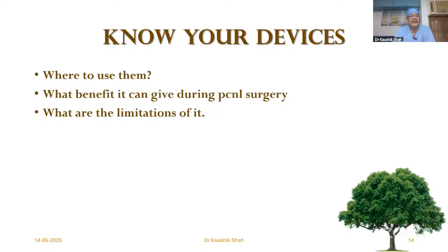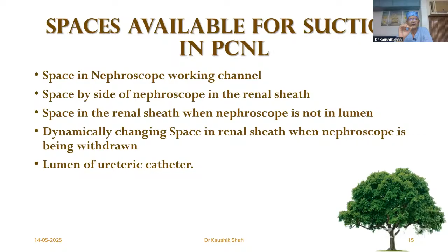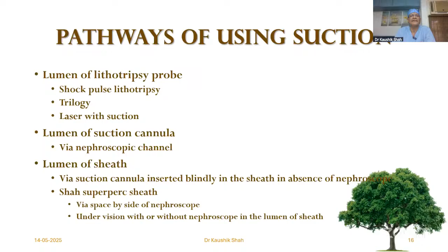So, coming to the suction, the spaces available in PCNL for the suction are the nephroscopic working channel, the space by the side of the nephroscope in the renal sheath, the space in the renal sheath when the nephroscope is not in the lumen, and the lumen of the ureteric catheter. So there are different pathways of using suction. One is the lumen of the lithotripsy probe, and there are three different techniques: shock pulse lithotripsy, Trilogy, and laser with suction. Then the lumen of the suction cannula itself, and the lumen of the sheath, where the suction cannula is inserted blindly in the sheath in the absence of the nephroscope, and the Superperc sheath, where the full space is utilized.